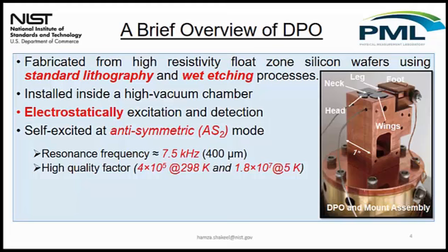Now, with high quality factors, we have a very high mass sensitivity, which is good for our application, where we basically want to detect around 20 micrograms drift over close to, I think, a year.